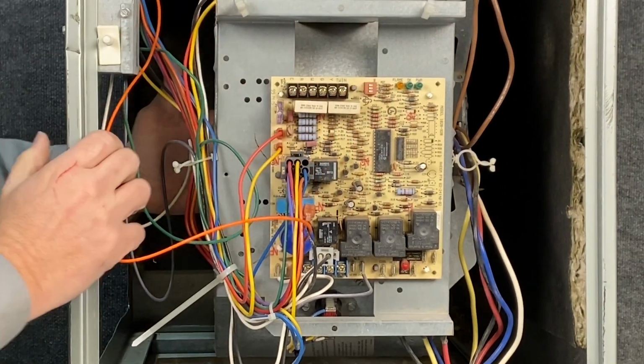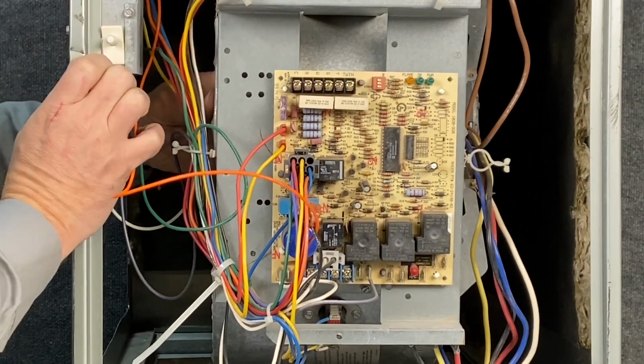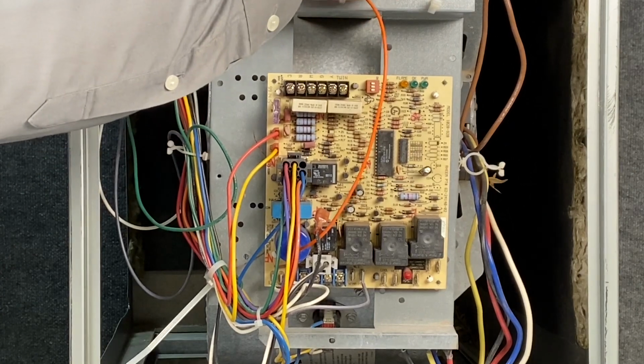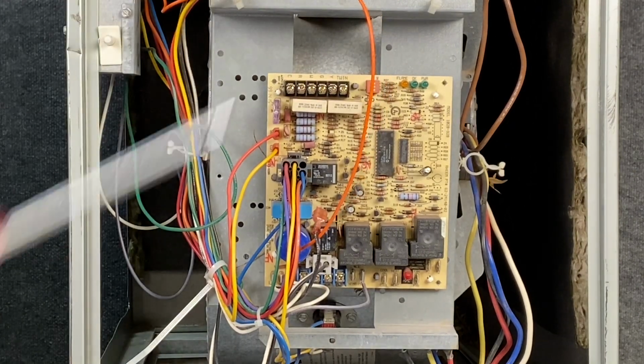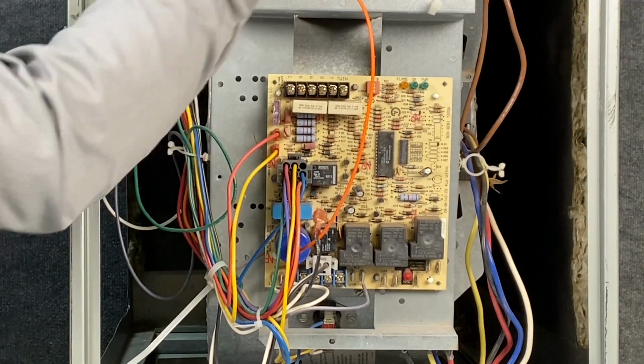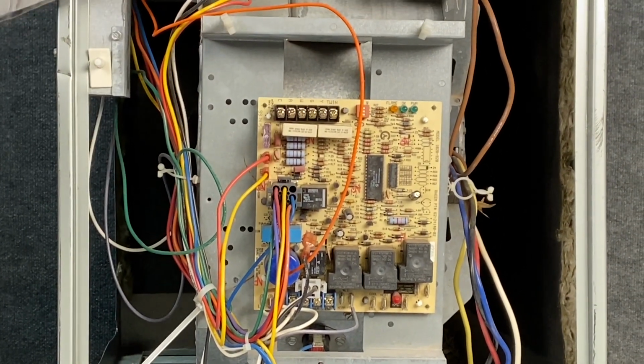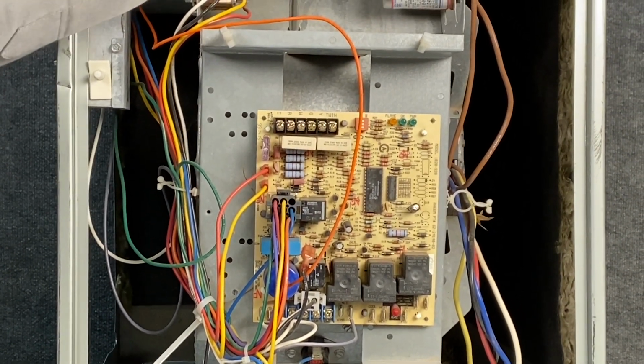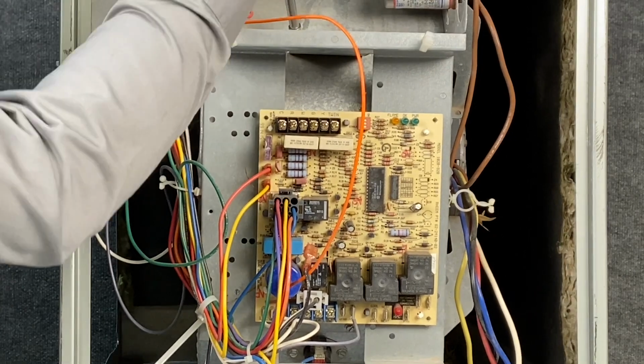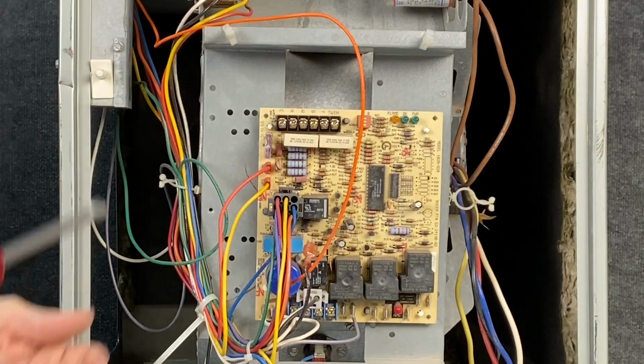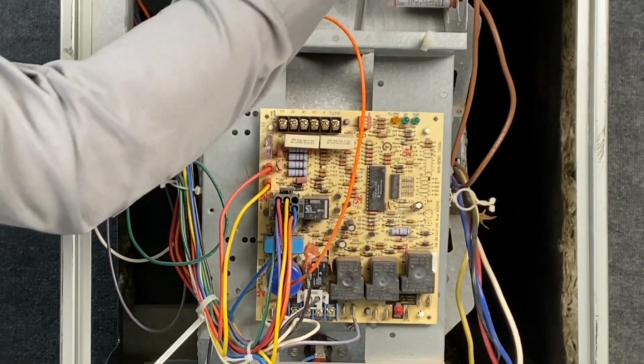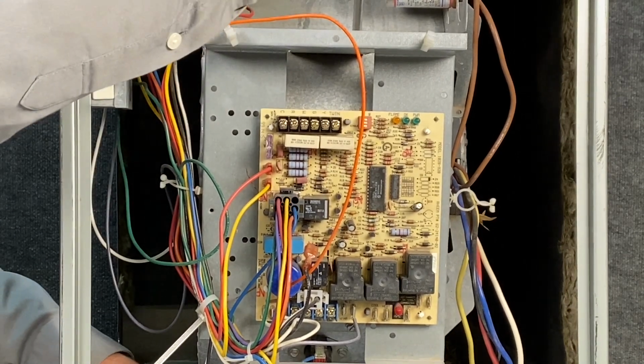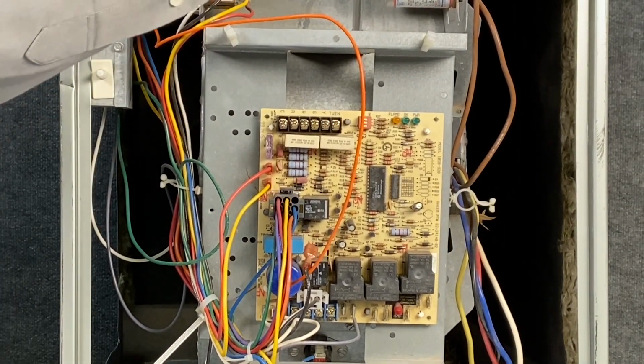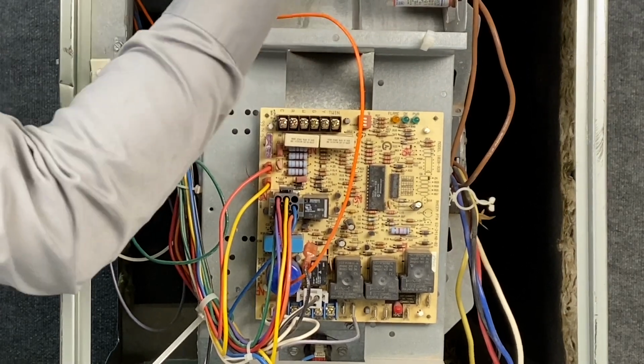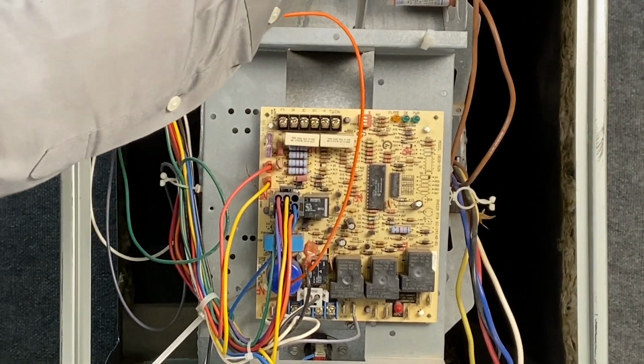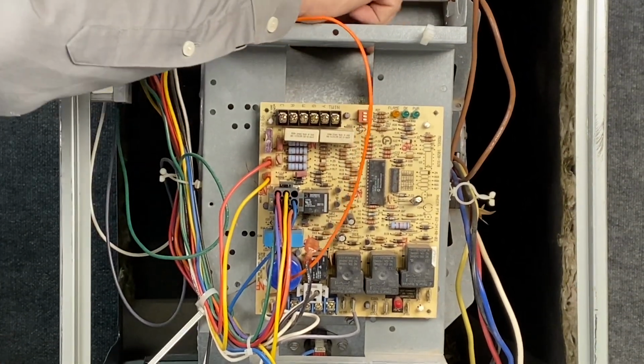So now I have a little bit more slack that I can pull this wire out. Now I can get to the bolts right here that hold this control board in. So I'm going to loosen that. Not really bolts, they're just screws. In this case, it's 1/4 inch. Most of the screws on these furnaces will be a 1/4 inch, or they will be 5/16. This particular brand, the RUUD brand, is famous for using 1/4 inch screws, which is very nice because you have the same exact nut driver for everything.